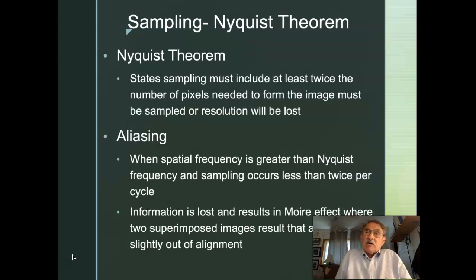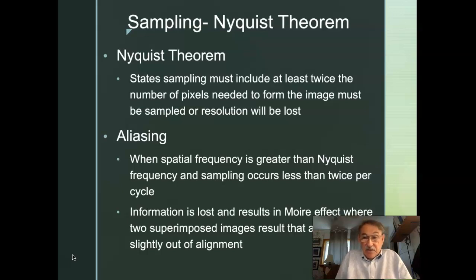Moiré effects often occur when we have used a grid in relationship to our image, and this is especially true in the CR system. If the grid lines run parallel to the way that the image plate has been scanned, we get an image that is slightly out of alignment — a Moiré effect. They don't enhance your radiograph and typically, when you have a Moiré effect, you're going to have to repeat that image.